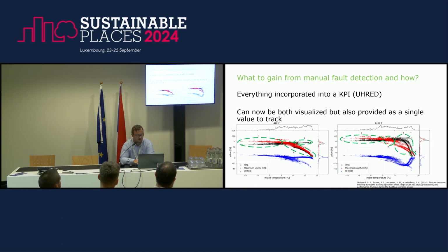So if you look at the green marked areas, we have the first area to the left for both air handling units. In this case, we're in the winter situation. We have heat recovery efficiency that's lower than what we could maximally use. The heat recovery efficiency is the black one, and the maximum useful heat recovery efficiency is the red one. In this case, we could consider if we needed a better heat recovery, a better rotary heat exchanger. It might not be worth it, but it's not an issue. We have a heating coil to compensate for exactly these situations.